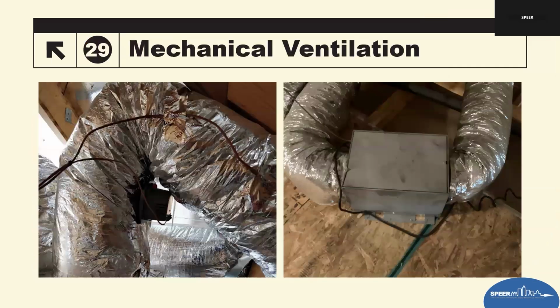So things like this happen all the time. And don't forget, mechanical ventilation, nine times out of 10, these are tied to the return plenum, which means they are part of the duct system. They do have to follow the same requirements of ACCA for installation. They also have to be part of the testing. So we need to make sure that these are being handled properly as well.